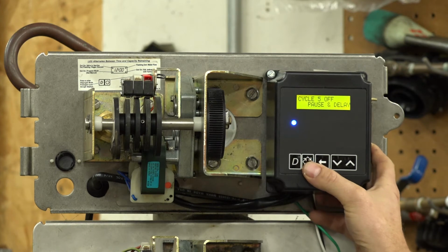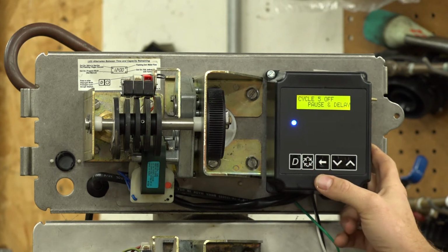For a simple example, if you had a 10 cubic foot unit, you wanted the salt at 15 pounds per cubic foot, you'd need 150 pounds of salt. With a 5 gallon per minute refill control, it's going to be 15 pounds of salt per minute. So 10 minutes would give you that 150 pounds.